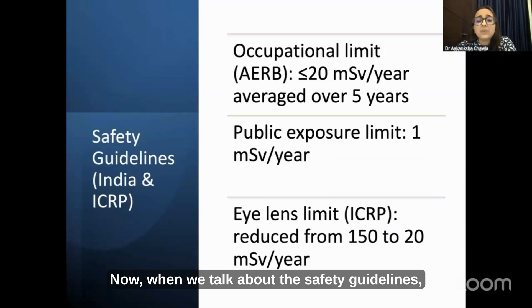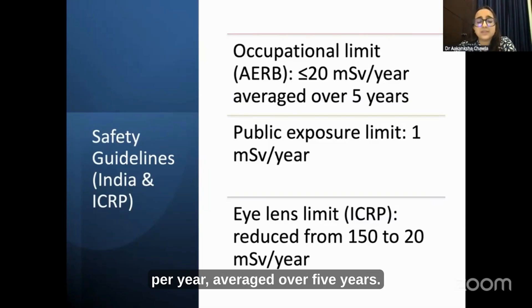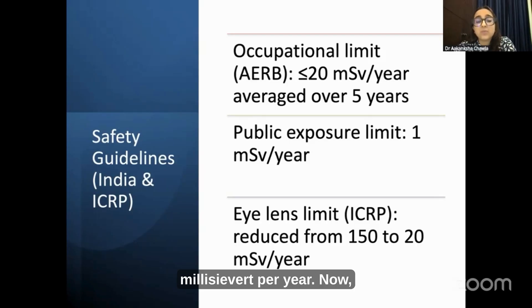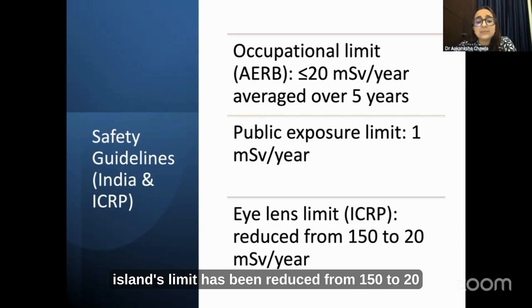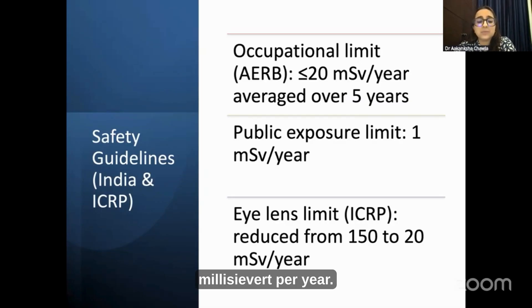When we talk about safety guidelines, the occupational limit is less than 20 mSv per year, averaged over 5 years, and the public exposure limit is 1 mSv per year. The lens limit has been reduced from 150 to 20 mSv per year.